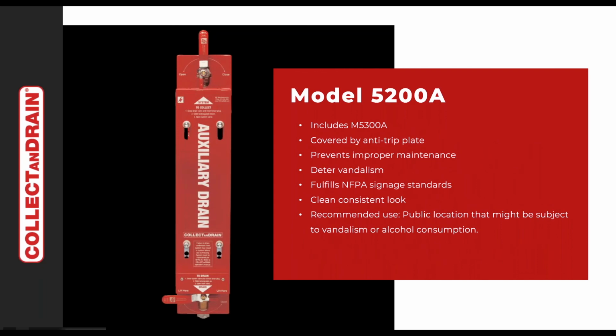But one of the areas that we focused on when we talked to contractors about what the ongoing problems with low point drains were, they said it was twofold. And the first one was people vandalizing the systems because they would be rotating the valve handles on the units, not knowing that they are potentially impairing a system. Again, speaking specifically to the Philadelphia area, but if you guys have ever been to stadiums, you'll see a lot of these in stadium environments. And I've been to ballparks and seen people just turning the valve handles while they're waiting to get a beer. So the first request from the commercial sector was, could we make these units lockable and prevent somebody from inadvertently activating the lower valve, which would dump the air out of the system?